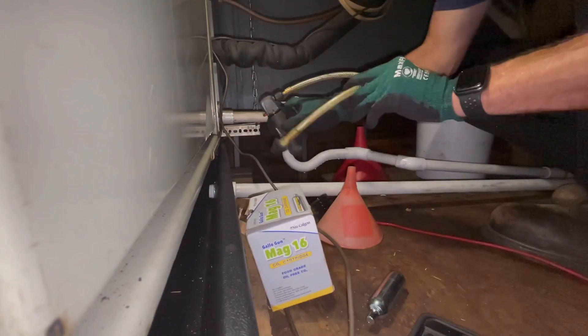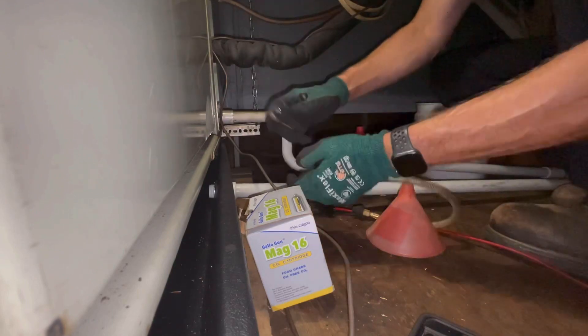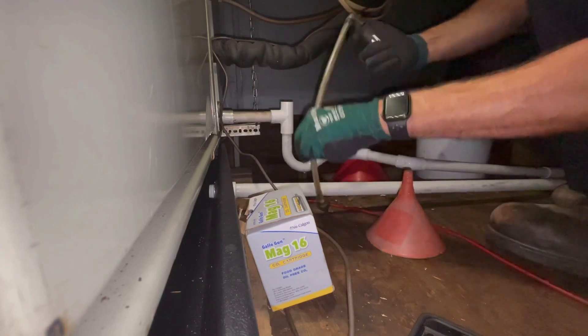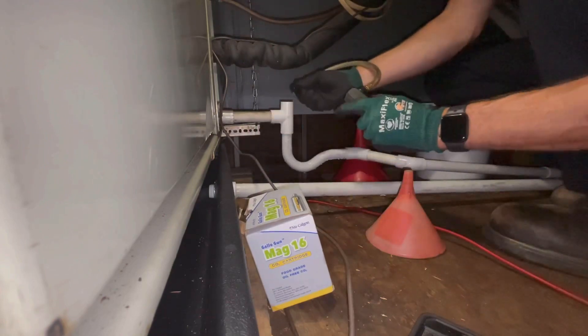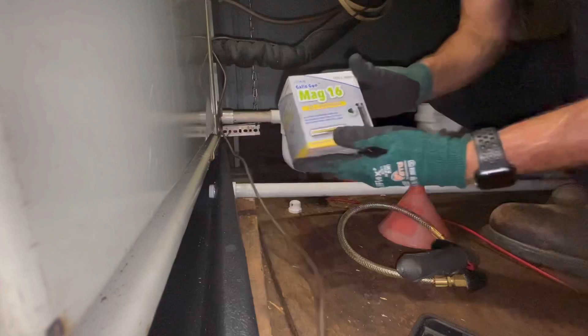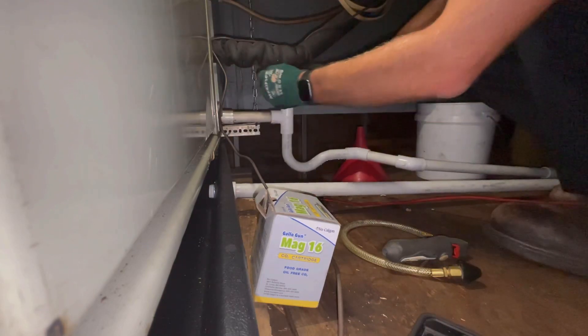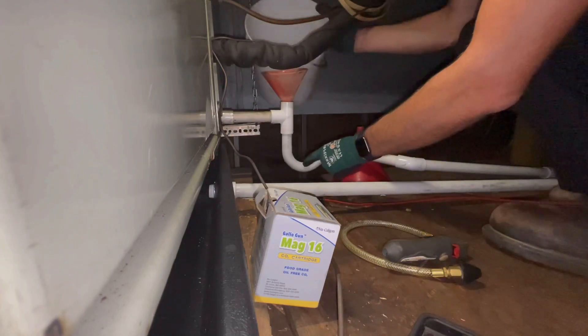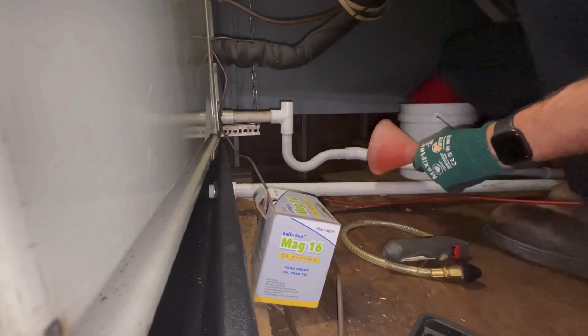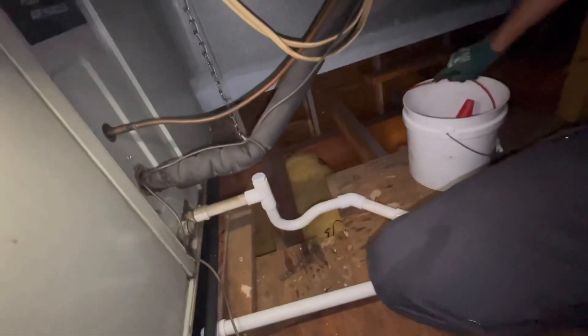After that, I take my Gallo gun — this is a CO2 packet-powered tool. Open that up, put your CO2 packet in, crank her down. You set that right on top and use that pressure — that's all it is, just some CO2 packet pressure. Now, always, always fill that trap. If you do not, there are times where this is piped directly into a stack pipe, and without that column of liquid plugging up that trap, you will get an odor of sewage gas coming up, going right back into that air handler — and believe me, your customer does not want that. Nobody wants to smell that sewage gas. Then put your cap back on, and we've verified that our drain is clean and clear.